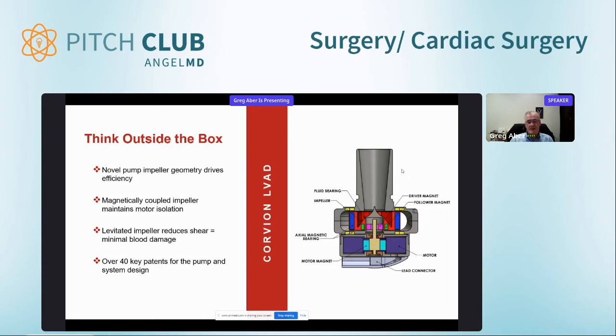And then we couple that impeller to a motor with a magnetic coupling. So the motor is completely separate and does not see blood of any kind. So only the pump chamber sees blood. And then lastly, we have to levitate the impeller so that we don't have blood damage. And we're able to do that with small permanent magnets rather than large electromagnets, which are used in the Abbott device. And we're able to maintain a very stable levitation of the impeller with just permanent magnets, no sensors or electromagnetic coils required. This allows for large gaps above and below the impeller for blood to flow in and out of the device without creating high shear.